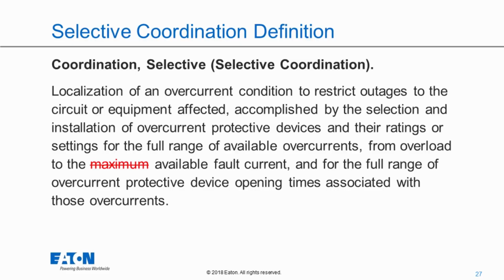Now, they deleted the term maximum because in the 2020 code, as you'll learn next session most likely, they now have a definition of fault current and available fault current. And available fault current is simply the largest amount of current that can flow at a given point in your system. So we deleted the term maximum because now available fault current is defined as the maximum or the largest. And we also have to consider that for the full range of overcurrent device opening time.